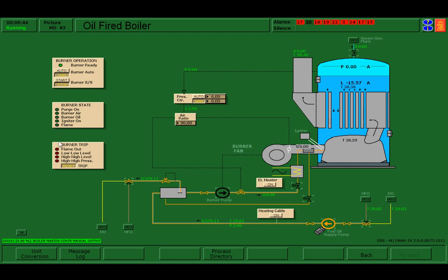If everything is good, and I don't have any trips showing, I can start my burner. Burner is going to go through a purge process. I get an alarm showing just as my boiler control systems have now started up, so it's just realized the pressure's low. My pilot flame starts, and then my main flame becomes established. I'm going to come and look for certain milestones to have been met. One of them is that you have your flame on running off of diesel oil in manual at low firing.